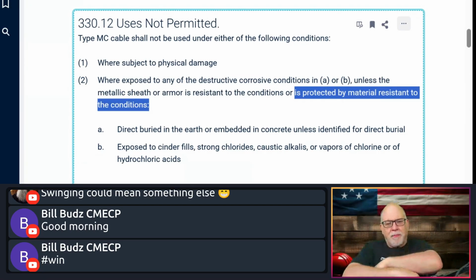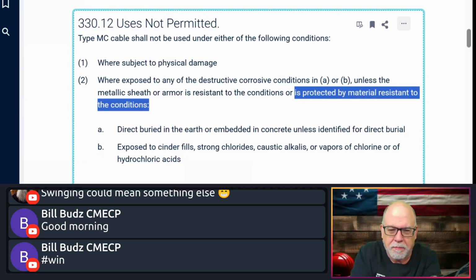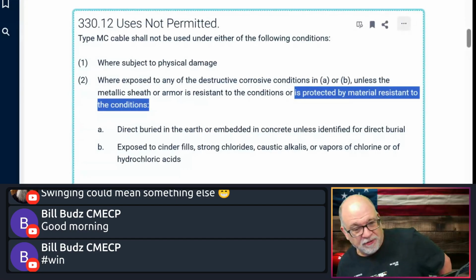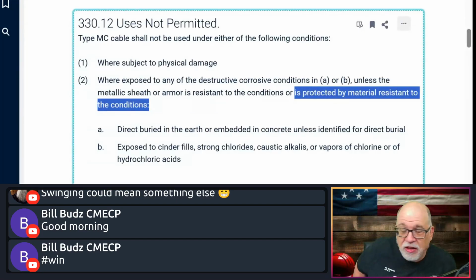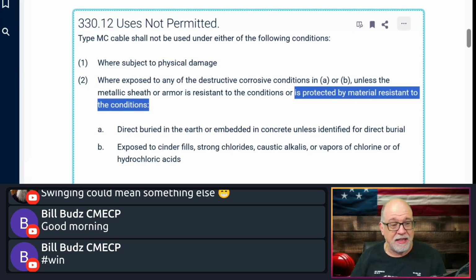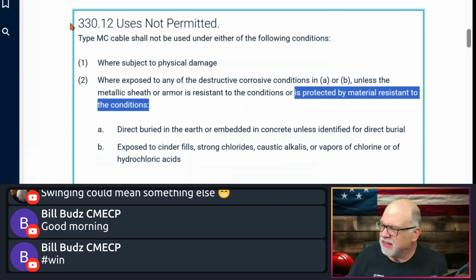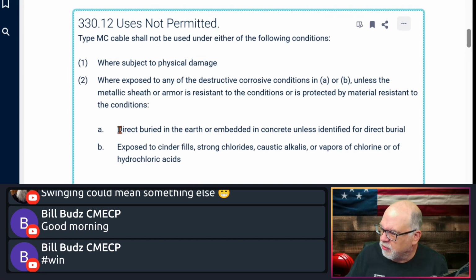Okay, so this is why people argue, because they don't understand, and this has been a big argument in Code Panel 17. PVC jacketed MC: PVC is very resistant to corrosive conditions as long as you don't damage it during the install. Take extra precaution. It does have a protective material that's resistant to these conditions. That's why it's marked direct burial. That's why you should be able to use it in a pool room or pool house, applications like those. Why? Because it is very resistant to corrosive conditions. And you've got to use proper fittings anyway. So at the end of the day, not an issue.